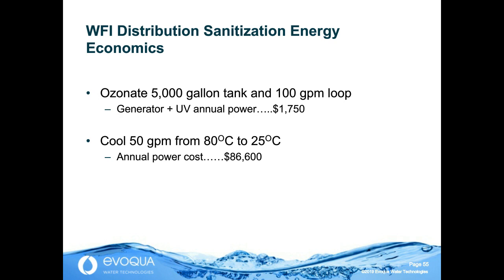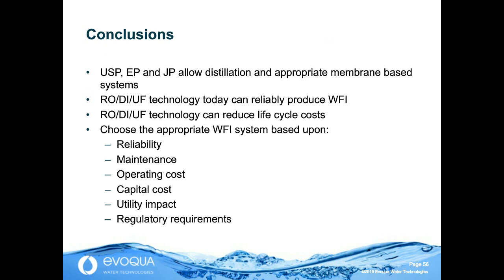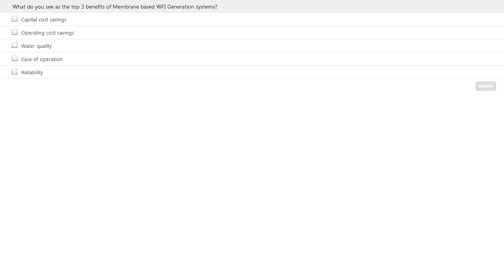So where does this bring us? It brings us to the point now that on a nearly worldwide basis, systems do not have to be distillation. They can be alternative process, such as reverse osmosis, continuous deionization, and ultrafiltration. Those systems have been long proven both in pharma and in other markets. They can offer significant life cycle cost reduction. And there are many things to consider when picking the right system: reliability, maintenance, operating cost, capital cost. The utility cost is part of operating cost, but utility impact is you may have a drastically reduced steam requirement, a drastically reduced chilled water requirement, and so there may be additional capital savings to be realized in the utility plant, and of course the regulatory requirements.